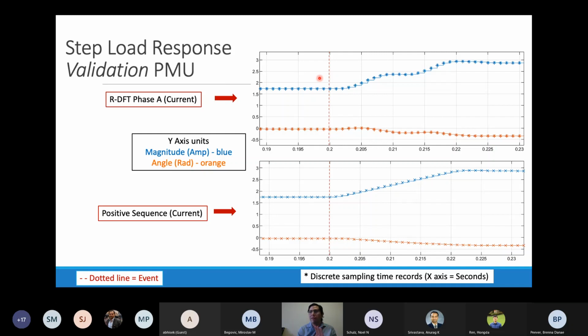We know we have three different phases, so we're testing here to show the different phase A. And on the bottom one, I'm testing the same scenario in a positive sequence calculation of the current. We can see the responses are as expected. This signal is better to detect because we are converting the three phase signals into one positive one. And we can see that in a matter of a cycle, we were able to reach a steady state in operation, which is common post-disturbance in all DFT models.